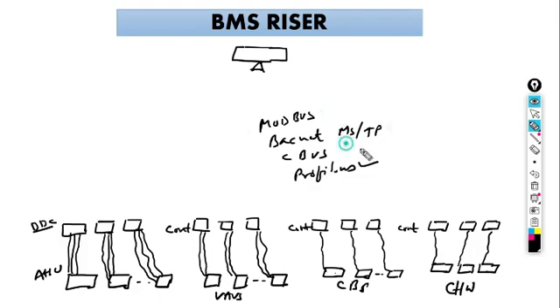The most common and easiest protocol is BACnet: Building Automation Control Network, master slave over token passing. This is the name of the communication protocol. This is the language through which they talk with each other. Now we need to connect all the DDCs together, right? We need to loop them so that they can transfer data among them and work in coordination. So these are the communication protocols which are going to be used.